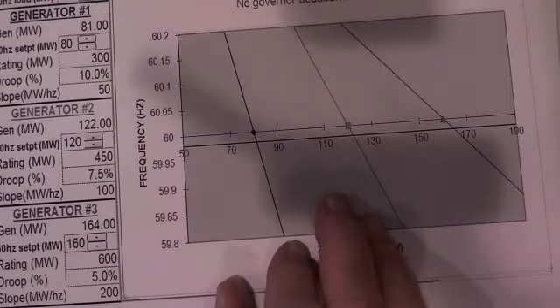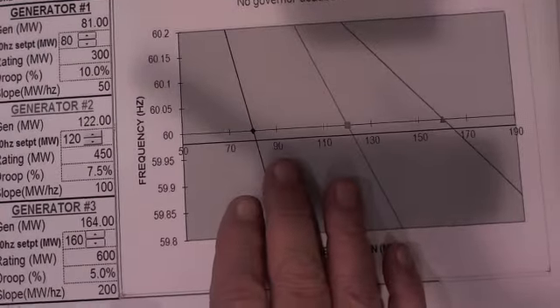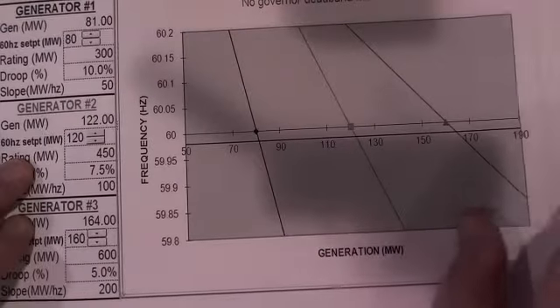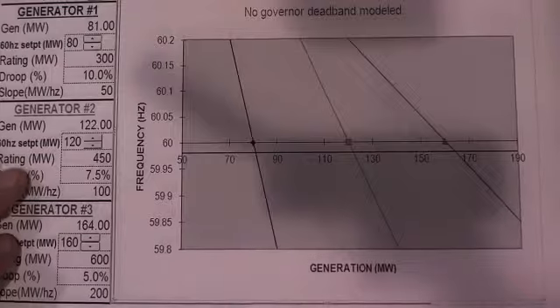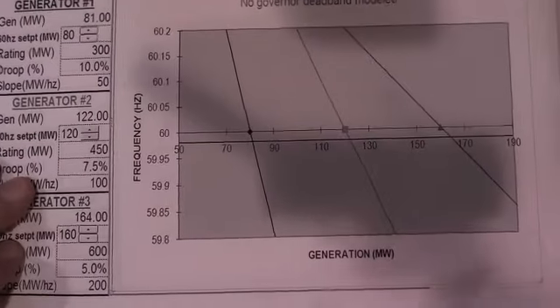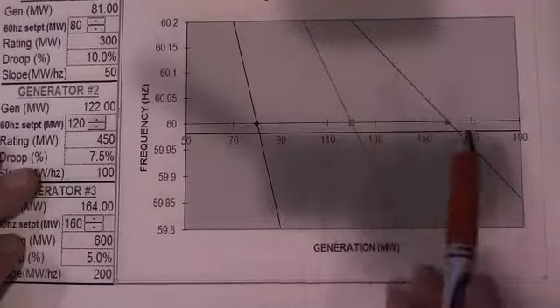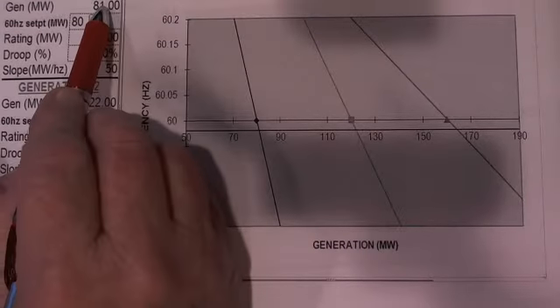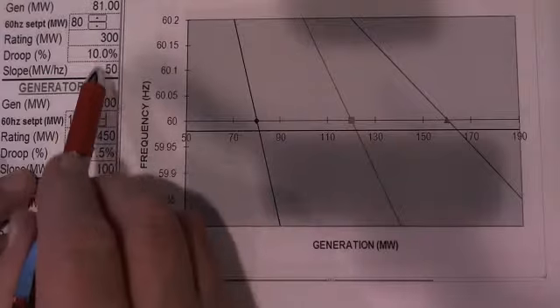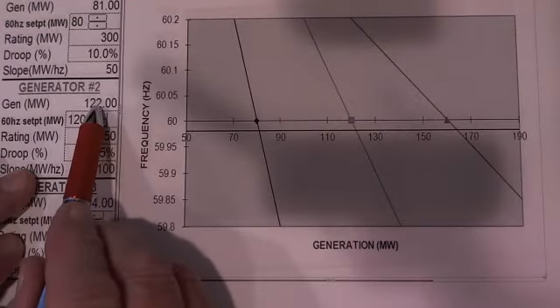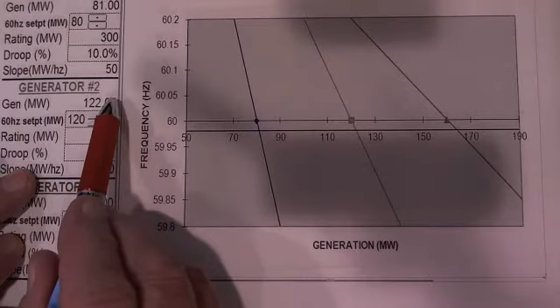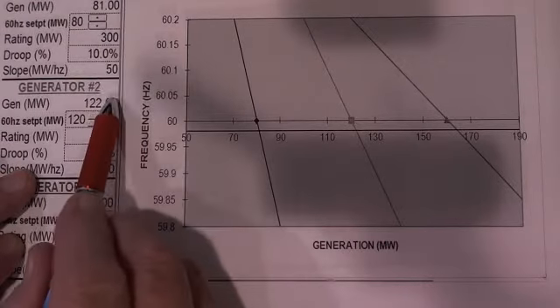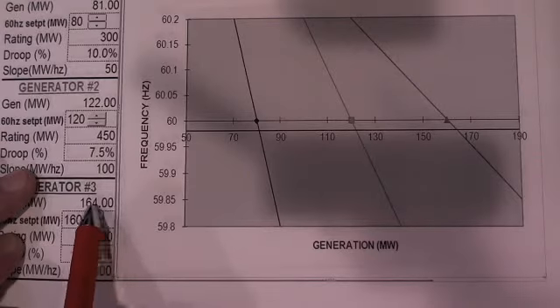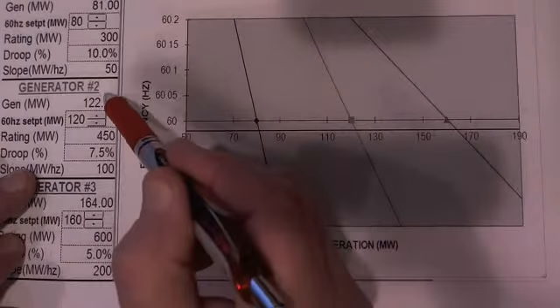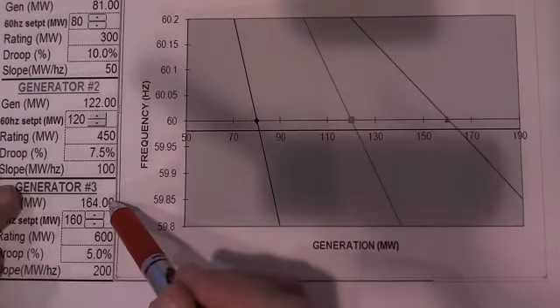and now all of a sudden the load changes to 367. Okay, and he picked those numbers. Bob is like me, picked the numbers so that he could teach you, but you didn't have to worry about decimal points. So this one goes to 81, so that's an extra 1 megawatt. This one goes to 122, that's an extra 2. So we've picked up 3, 1 here and 2 more here. And this one goes up to 164, it's picked up 4. There's the pickup of 7. 1 extra here, 2 extra here, and 4 extra there.